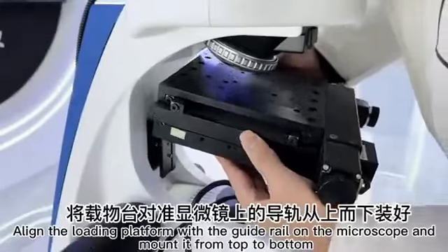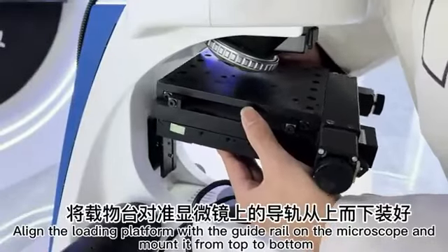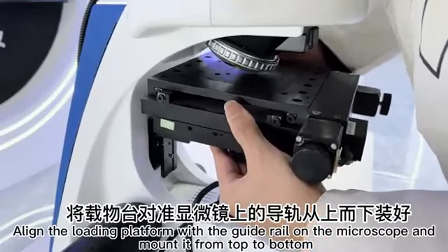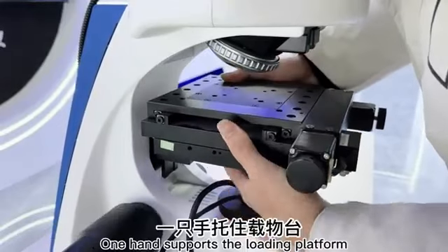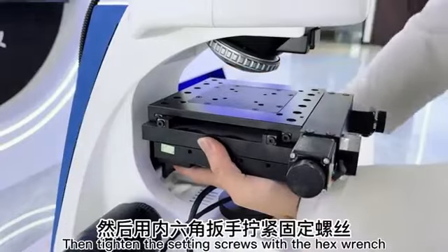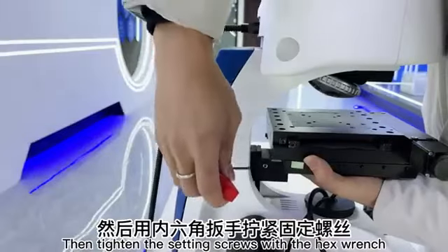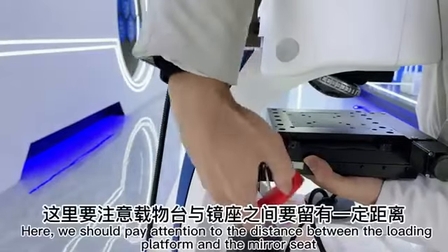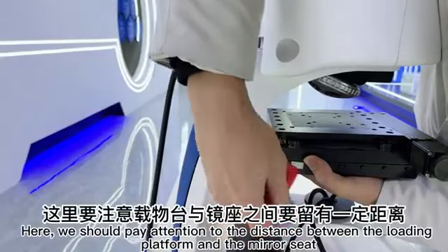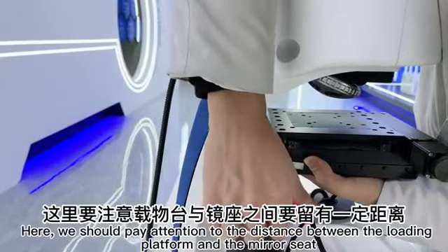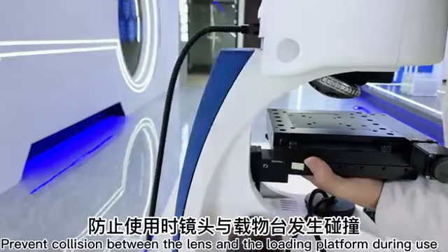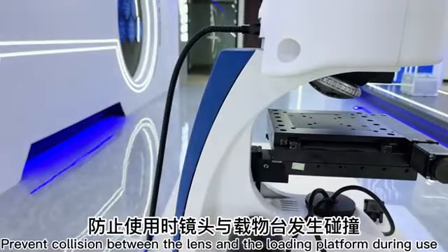Align the loading platform with the guide rail on the microscope and mount it from top to bottom. One hand supports the loading platform. Then tighten the setting screws with the hex wrench. Here, we should pay attention to the distance between the loading platform and the mirror seat, to prevent collision between the lens and the loading platform during use.